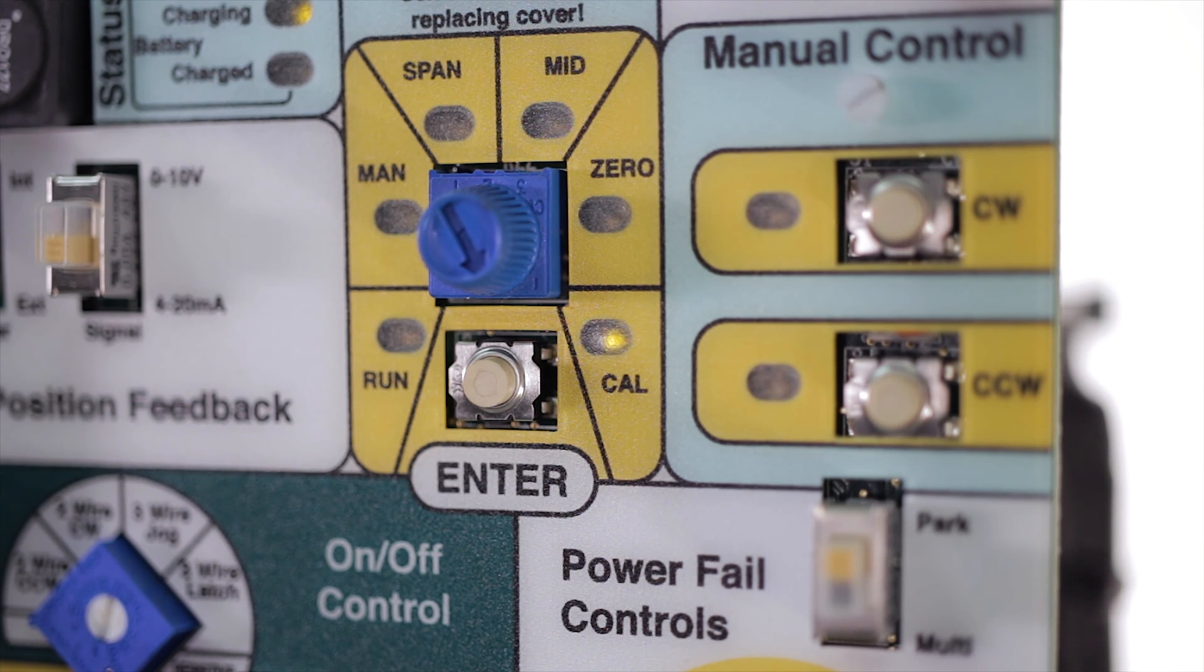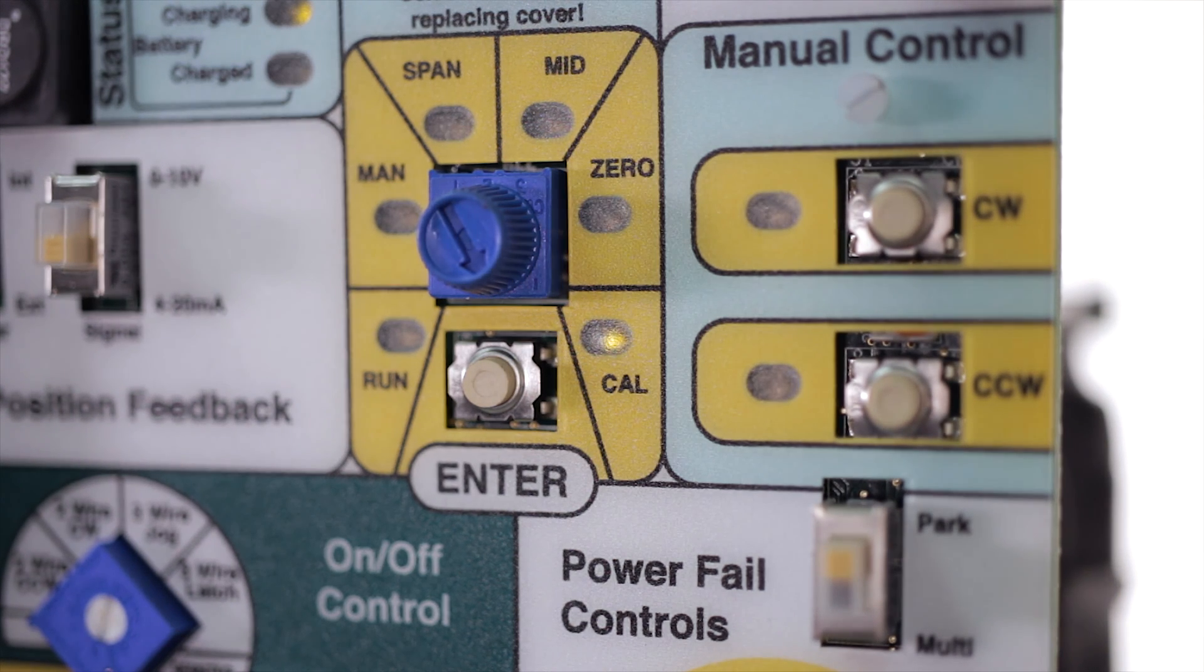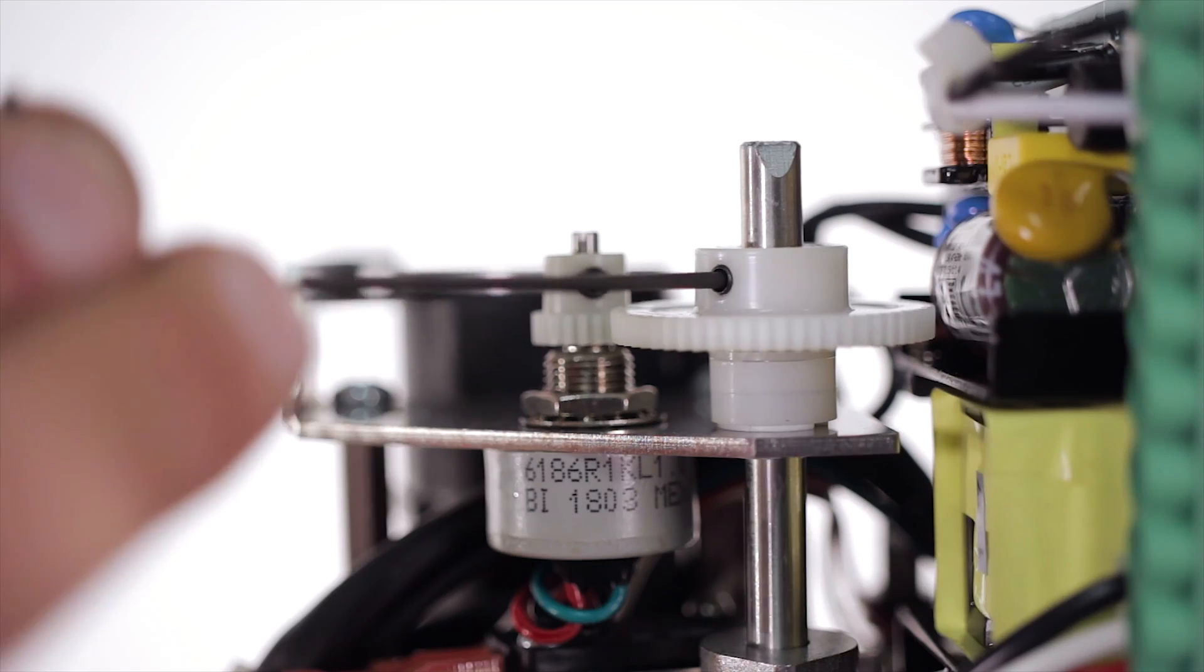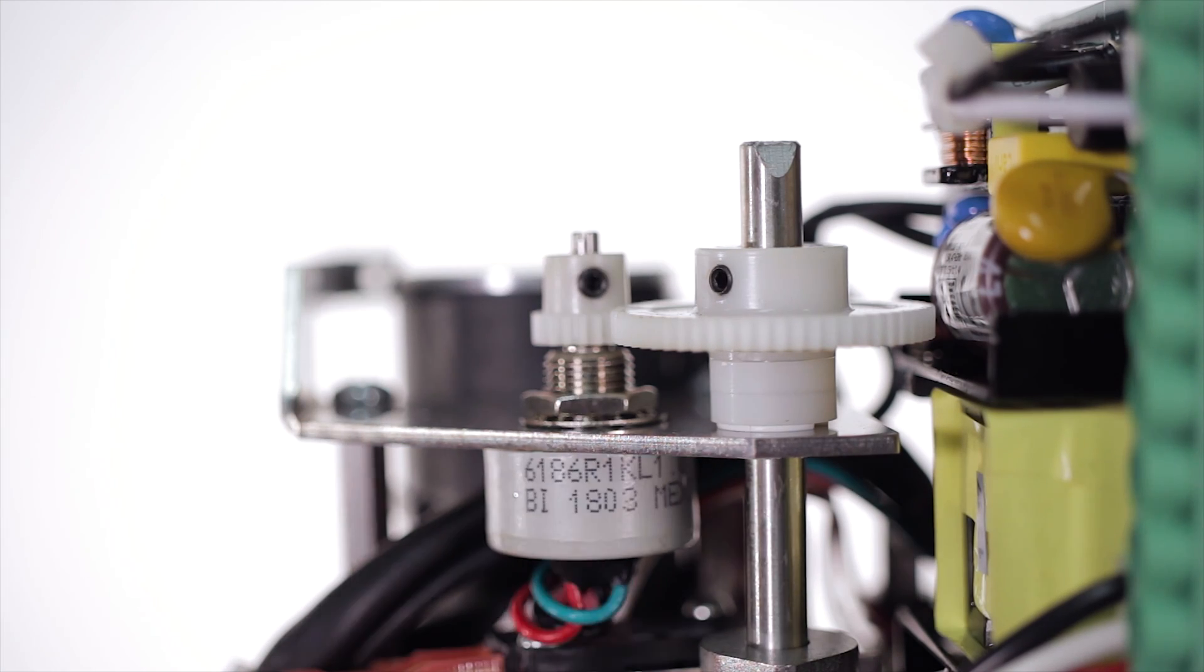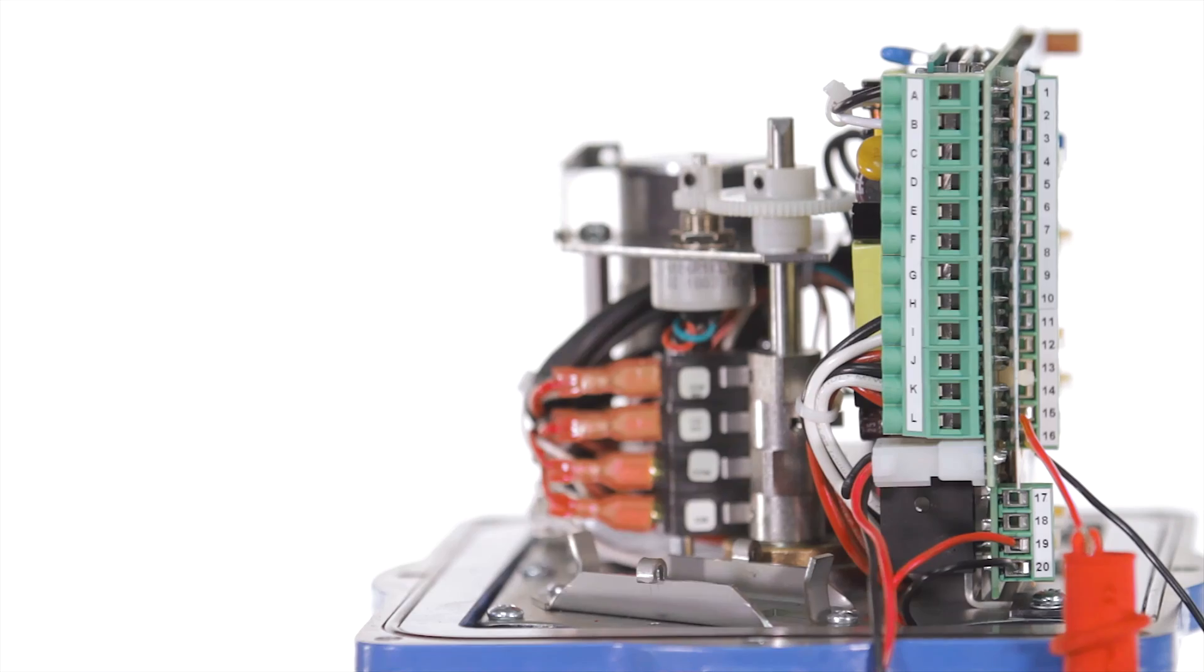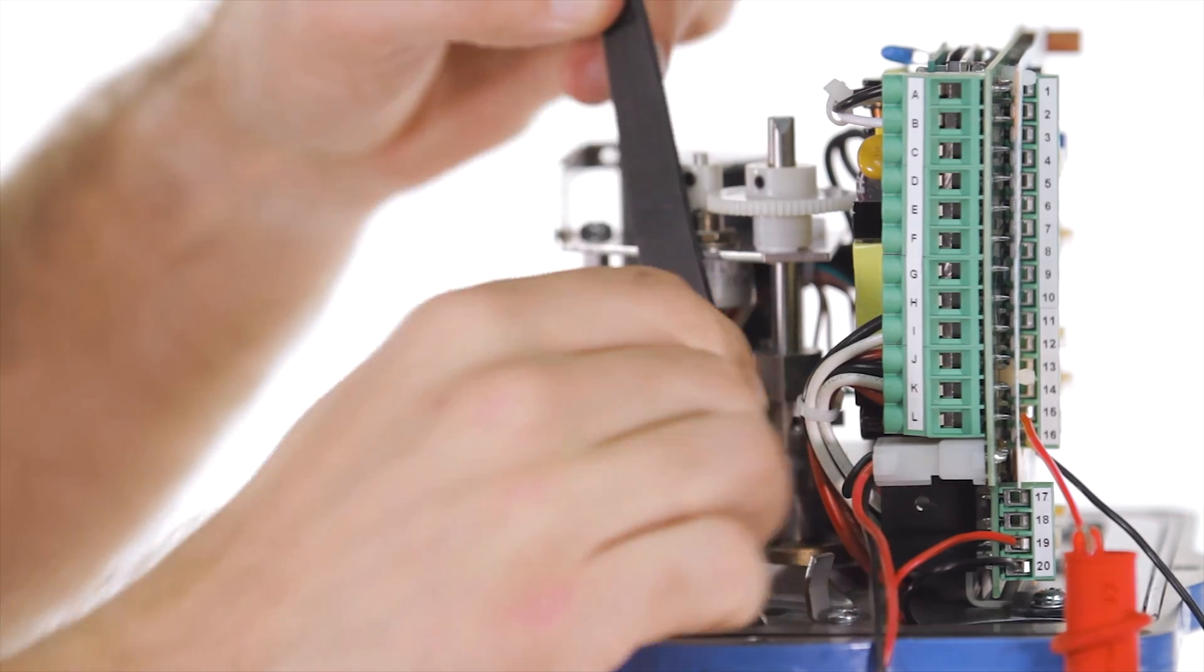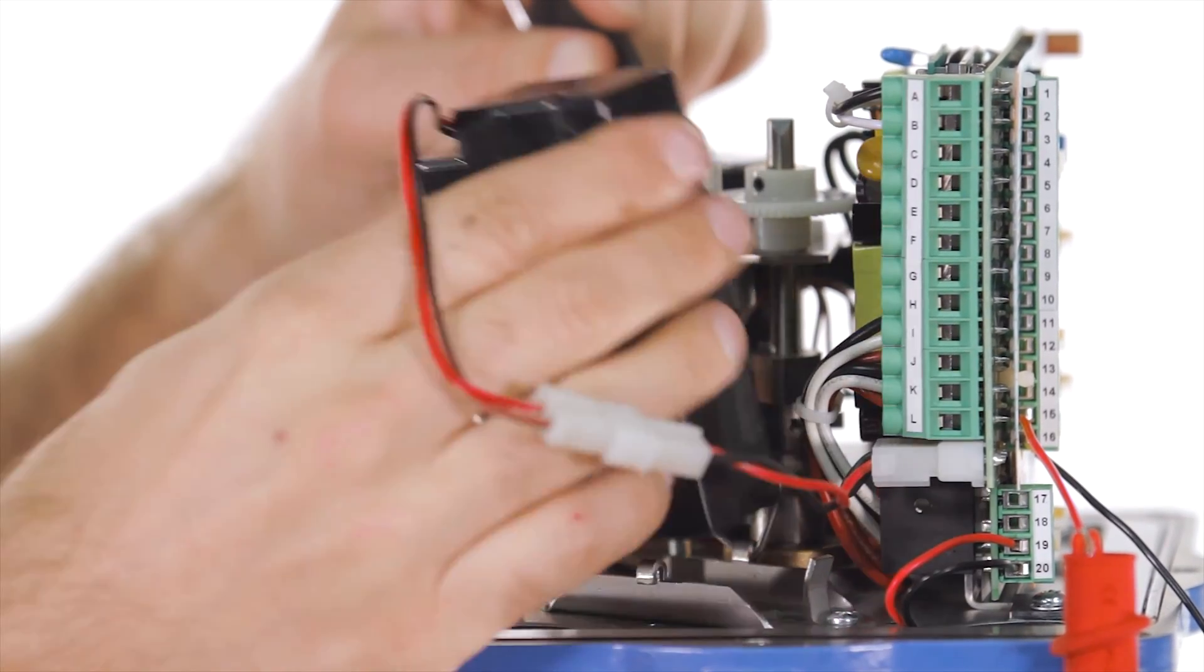The LED light will blink faster and faster as you get closer to calibration point. When the calibration LED is solid retighten set screw on the main gear then push the enter button. Now that your potentiometer is calibrated you can replace your battery.